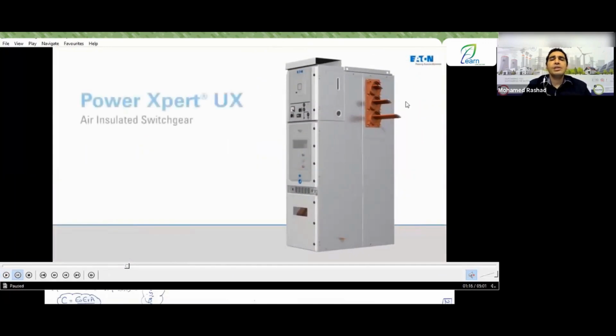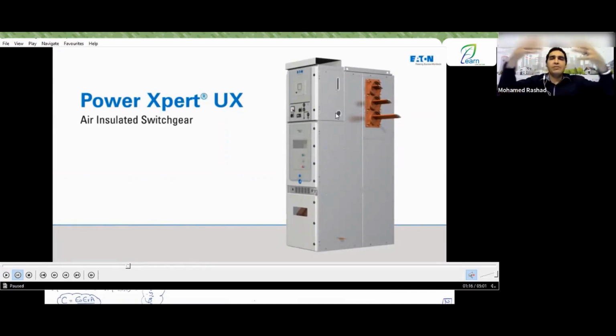So this is the switchgear. As you saw, Engineer, it is an air-insulated switchgear, referred to as AIS. What does air-insulated switchgear mean, Engineer Rashad? As you saw, the bus bar is in the air, around an insulating material, no problem. The switchgear cables, everything is initially present, unlike gas-insulated switchgear where all of this is inside tubes.